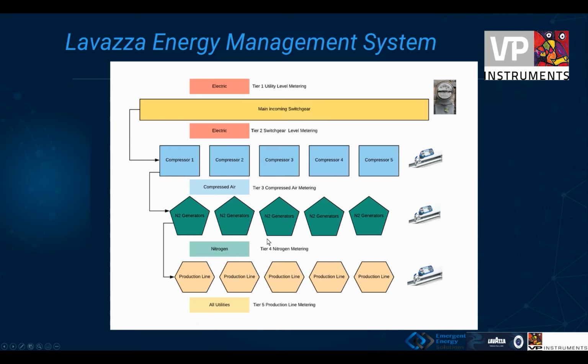From that point, we meter all the overall nitrogen generated from all of their nitrogen generators. The site has 18 nitrogen generators that put out about 500 CFM of nitrogen continuously to feed their production lines.